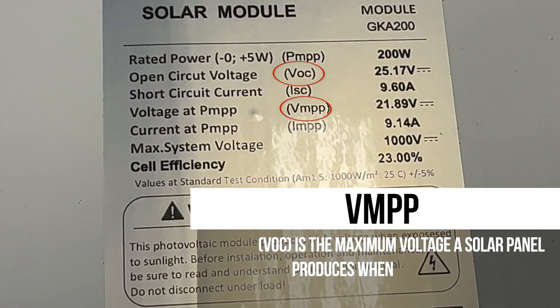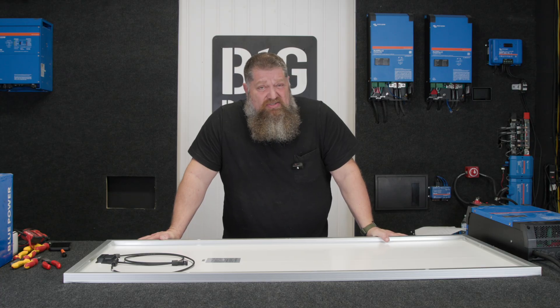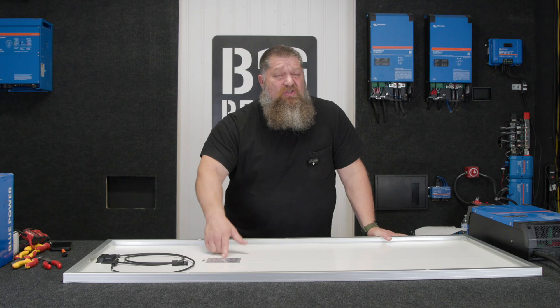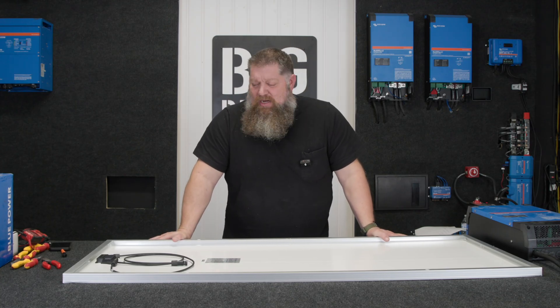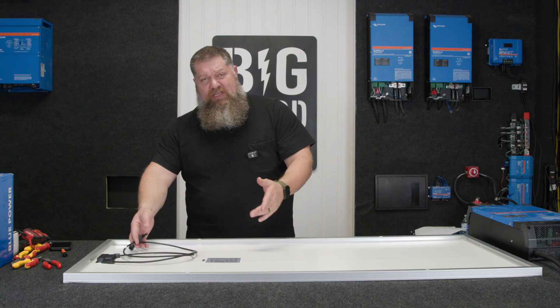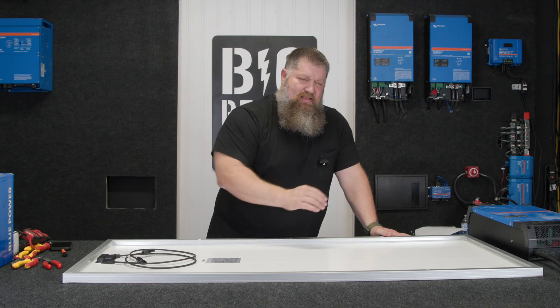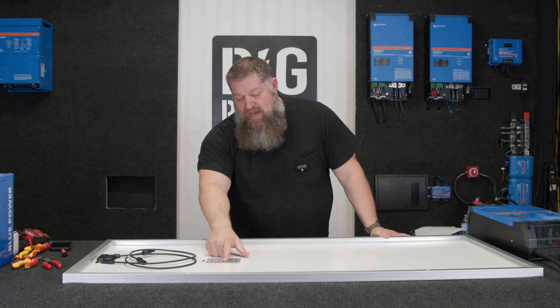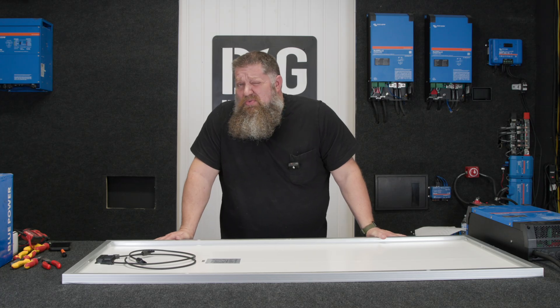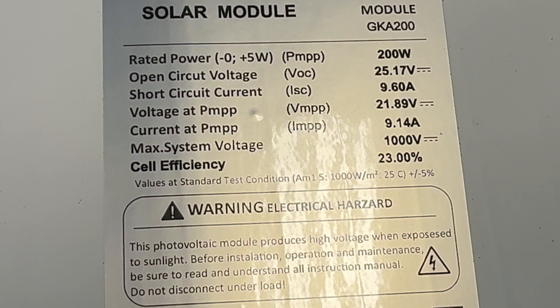Then you have another one that says VMPP — that's maximum power point. Voltage, just like anything else: if there is no current, we have a maximum amount of pressure, or potential. On this particular panel, the VOC is 25.17 volts. Without any load, if I were to take my multimeter and check the two terminals with good sun strike, I should see roughly around 25.17 volts. Whenever that pressure turns into flow, we're going to see that pressure drop. Under maximum power point, the voltage will drop on this particular one to 21.89 volts. So the question is: which one do we use to protect our solar controller? We always use the larger number — volts open circuit.